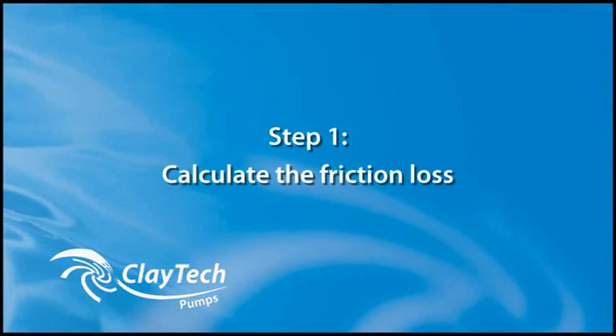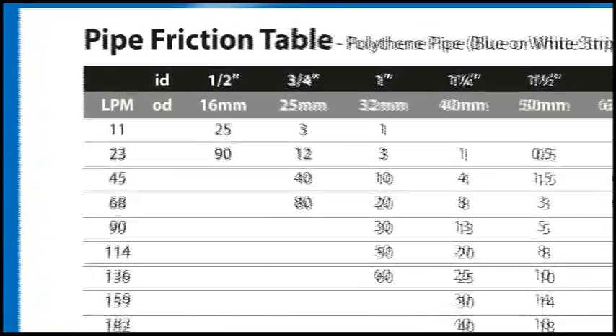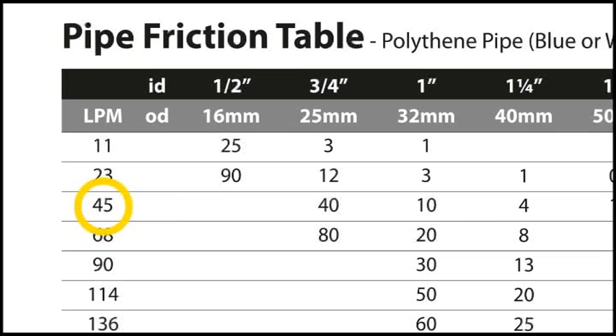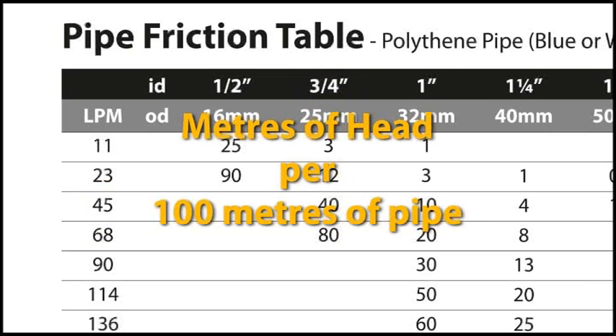The first step is to calculate friction loss. Remember, friction loss can be calculated using a pipe friction table. At 45 litres per minute, and using a pipe 3 quarter inch inside diameter, we can see that there will be 40 metres of pressure lost to friction. However, in this chart, all values apply to 100 metres of pipe.